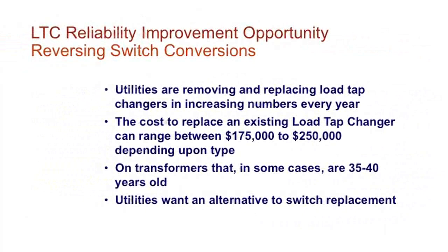The cost to do an LTC retrofit is around $175,000 to $250,000. Depends on the model of LTC that you have and the model that you're replacing it with. So there's a lot that goes in with that. That's why you see that broad band of cost, I would say, for an LTC retrofit. Basically, most of the transformers that we do the retrofits on are 35 to 40 years old. We've done some as soon as 15 years just because we're uprating the unit for that purpose. But in most cases, you find it's older units with the older LTCs.